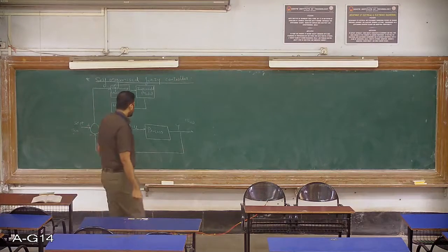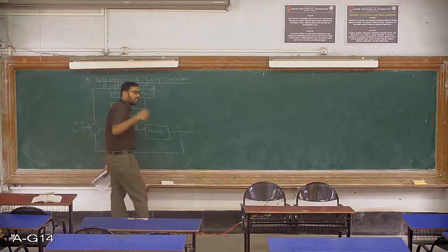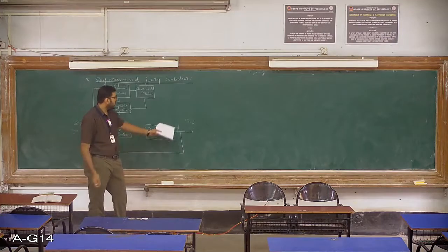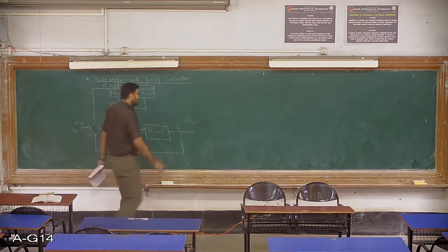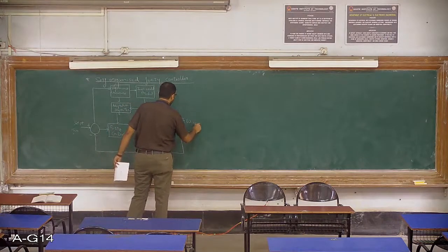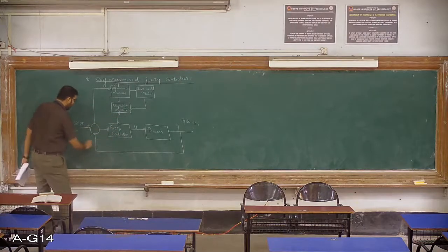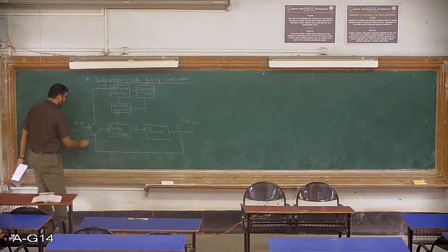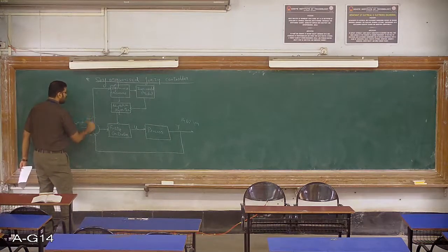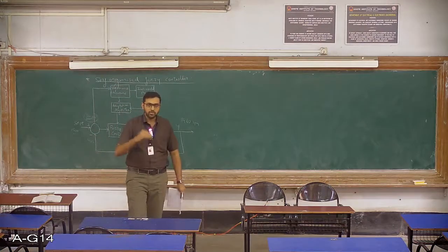But we cannot assure that every time you will be getting 1500 RPM, right? Because there is a variation with respect to the load or voltage, current, anything can be varied, because of which the system can change its speed. So let us say that the speed is something around 1480 RPM. Now this 1480 RPM will come back. As it is a closed loop system, the feedback will be given of 1480. So 1500 minus 1480 is 20 RPM. So the system will come to know that there is an error of 20 RPM. That means the speed is mismatched by 20 RPM.